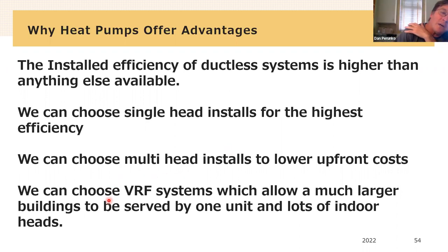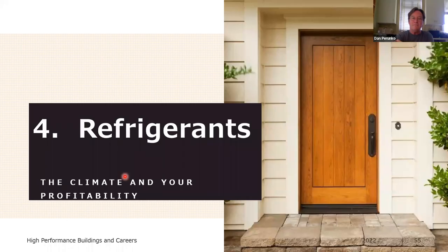And then I'm just going to touch on a commercial variation within the equipment called VRF systems. They're very similar to mini splits, have slightly lower efficiencies, but they're designed to have one big outside unit and a lot of inside units. They're usually used in commercial scenarios and they can be useful for big houses. I've only done one VRF system. I've done tons of different variations on mini split systems.